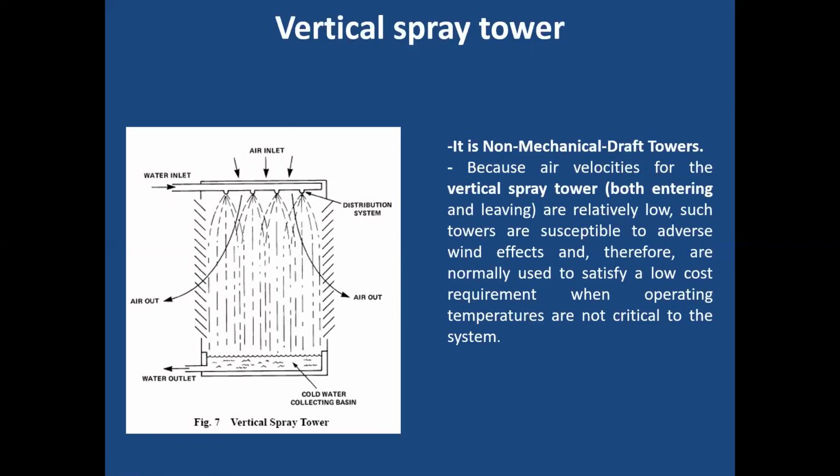They can be fitted inside the room, because if the wind is high, then with such a cooling tower there is a possibility of wastage of water, because due to wind effect, water can go outside the cooling tower. So more makeup water is required. But it is a slightly low cost cooling tower. No blower is required. Only with the help of a pump, if the water is sprinkled, then the required delta T can be achieved. This can be fitted inside the room as well as outside the room.